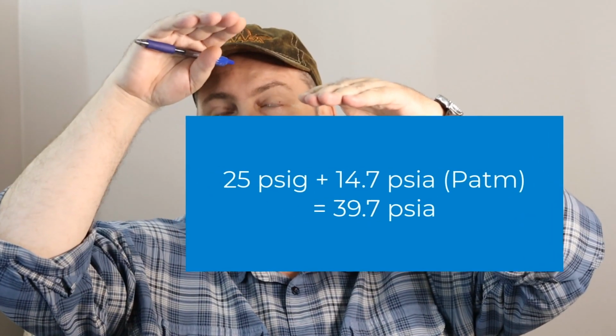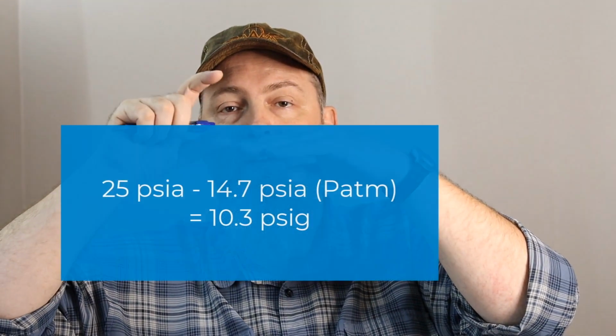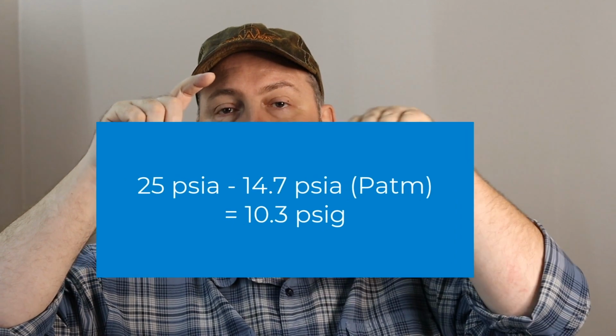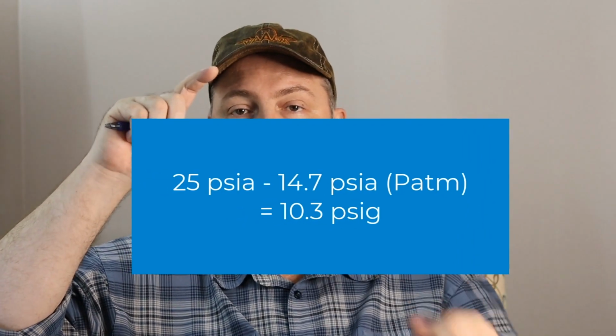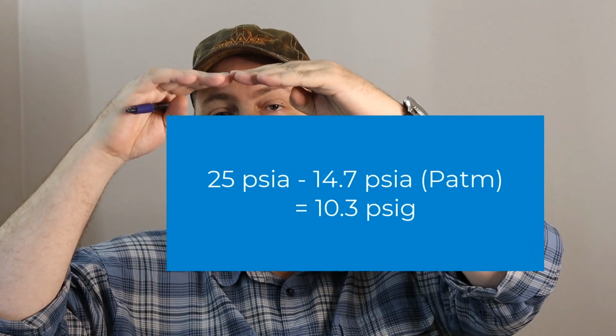39.7 PSIA. And then the same, let's say I gave you 25 PSIA, right? So 25 pounds absolute above actual 0. What is it in PSIG? Well, to find how far above the relative 0 it is, we subtract the 14.7, which leaves us with 10.3 pounds gauge above our relative 0 of atmospheric pressure. So 10.3 PSIG is the same as 25 PSIA. And you'll need to practice the same with the vacuum problems.